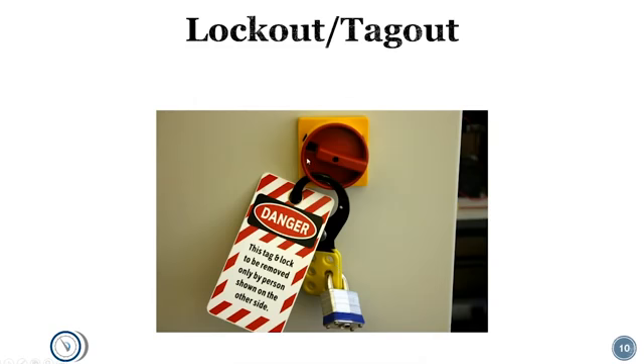It's very, very important, very practical. Certainly not, as some people think, overkill. It is definitely not. In a lot of cases, you're shutting off units at disconnects that are well away from where you're working, especially if you're working past the disconnect side. So say you're removing a rooftop unit or doing significant work, maybe to a disconnect on a rooftop unit. You have to definitely make sure that it's locked out and tagged out so that somebody's not going to accidentally come along and turn it on.